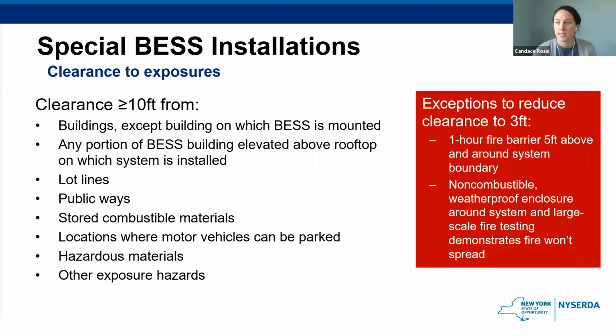So the special installations have a specific clearance to exposures as well. They have to have a clearance of at least 10 feet from buildings, except buildings on which the energy storage is mounted, any portion of the storage building elevated above the rooftop on which the system is installed, lot lines, public ways, stored combustible materials, locations where motor vehicles can be parked, hazardous materials, or other exposures. So I think the constant theme when it comes to clearance to exposures is you blatantly do not want your energy storage system being installed next to anything that might be combustible or might cause the project to act abnormally. You want to make sure the systems are secure from access and don't have other things too close to them to make anything go awry.